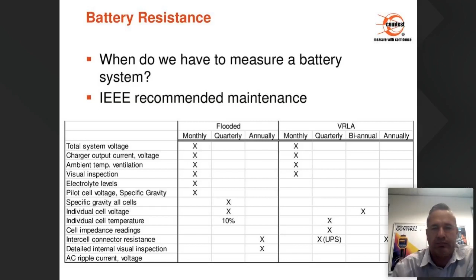For your valve-regulated lead-acid batteries: total system voltage monthly, charger output current and voltage monthly, ambient temperature and ventilation also monthly, and then visual inspection. Then quarterly, we will do the individual cell temperatures and the intercell connector resistance. Biannually, we can do the individual cell voltage, and then annually, we can also check the interconnector resistance. Interconnector resistance is important because those links or straps are connecting these batteries in series, and we could have corrosion on the links or the joints where they are tied to the batteries themselves.